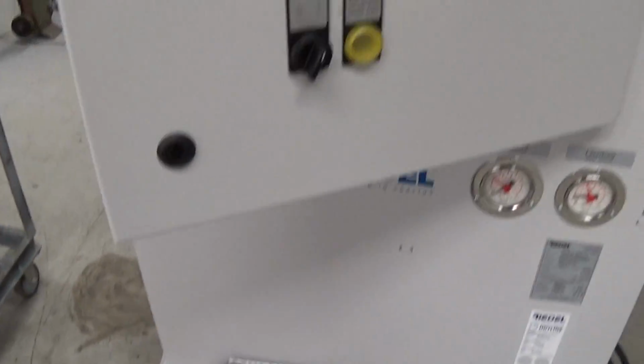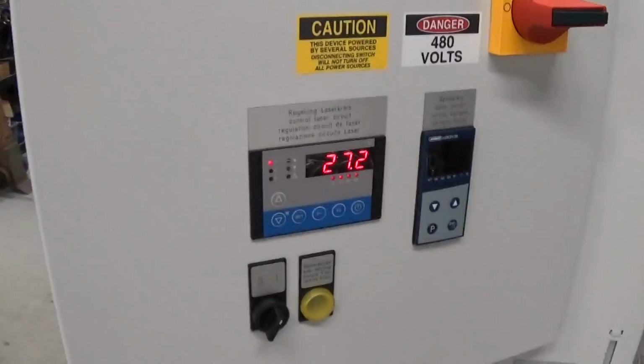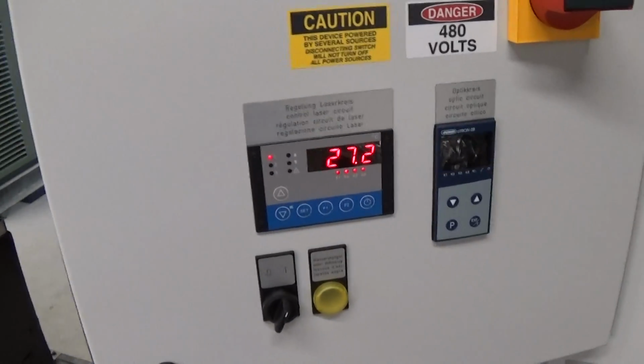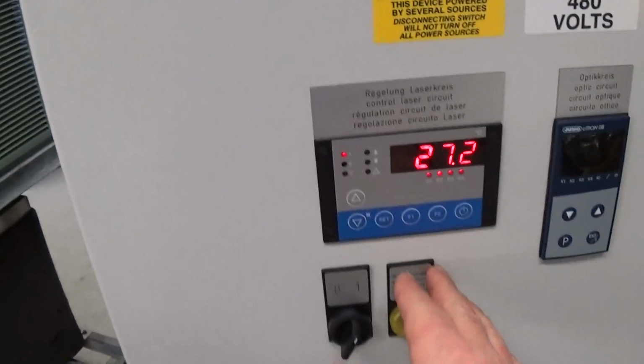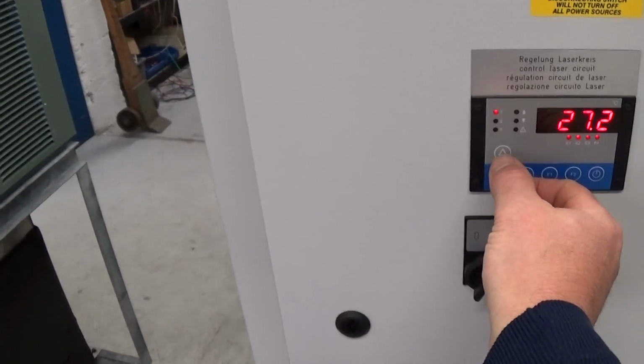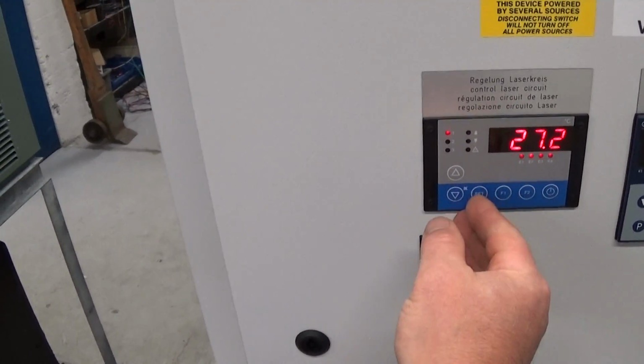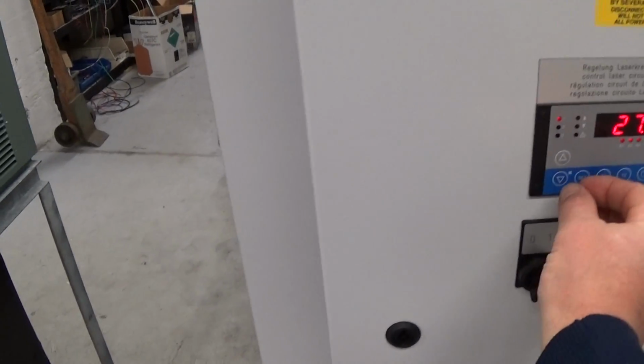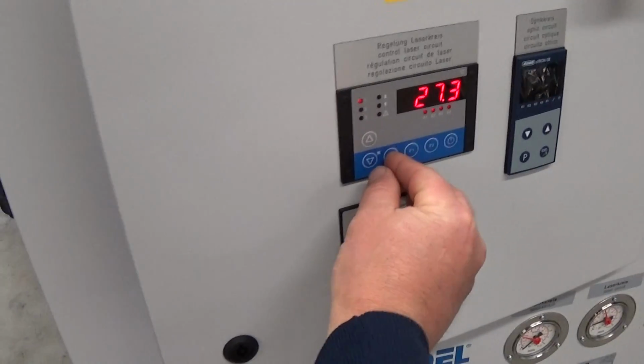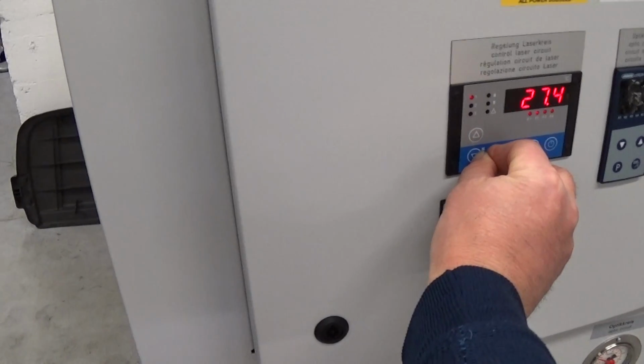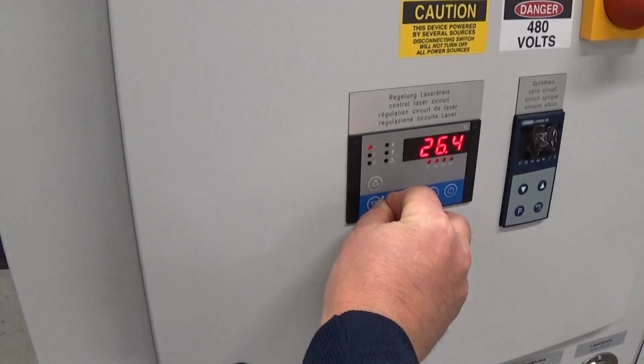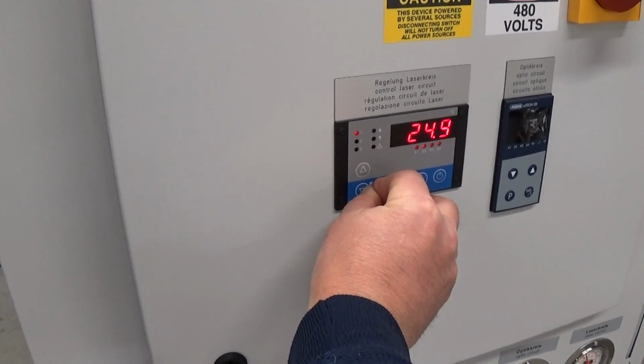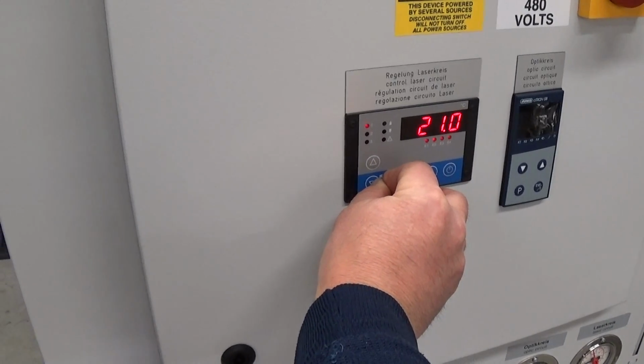So then the only other thing, after you check phase rotation, okay, and obviously get the unit piped up, and I'll talk about a couple other things in a minute, is you have to change the set point, it's up and down, okay, but you have to hold the set point in while pressing the other button. So we're going to hold the set point in, okay, and we're just going to bring it down to the coldest it can go, 21 C.